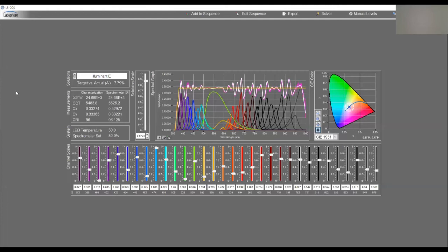With our FT2300, we have a tungsten halogen light source in there, which is a very stable source. We characterize the FT2300 for spectral radiance using that halogen source inside the sphere and the spectroradiometer inside the sphere, and a NIST traceable spectral radiance calibration through the port. That spectral radiance calibration is transferred to that tungsten source inside the sphere, and that can be used to recalibrate this spectral monitor, which is the pink line.